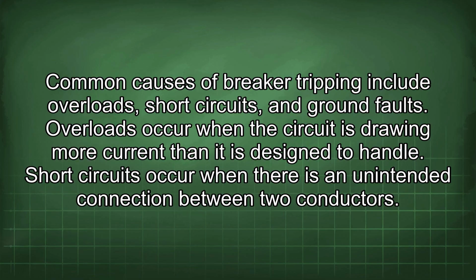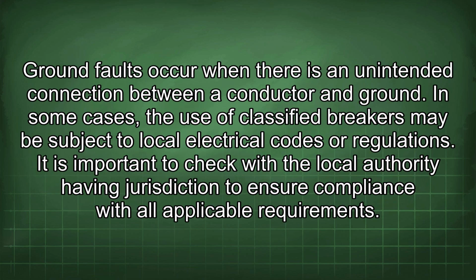Overloads occur when the circuit is drawing more current than it is designed to handle. Short circuits occur when there is an unintended connection between two conductors. Ground faults occur when there is an unintended connection between a conductor and ground. In some cases, the use of classified breakers may be subject to local electrical codes or regulations. It is important to check with the local authority having jurisdiction to ensure compliance with all applicable requirements.